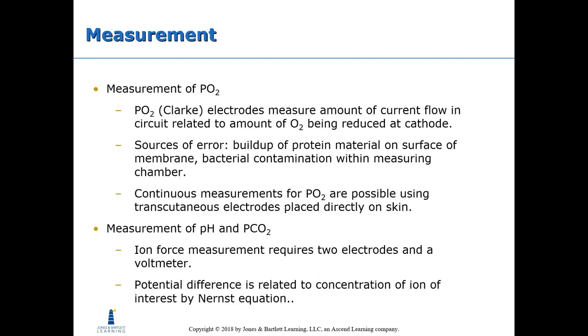Measurement of pO2 uses Clark electrodes, which measure the amount of current flow in a circuit related to the amount of oxygen being reduced at the cathode. Sources of error include the buildup of protein material on the surface of the membrane and bacterial contamination within the measuring chamber.